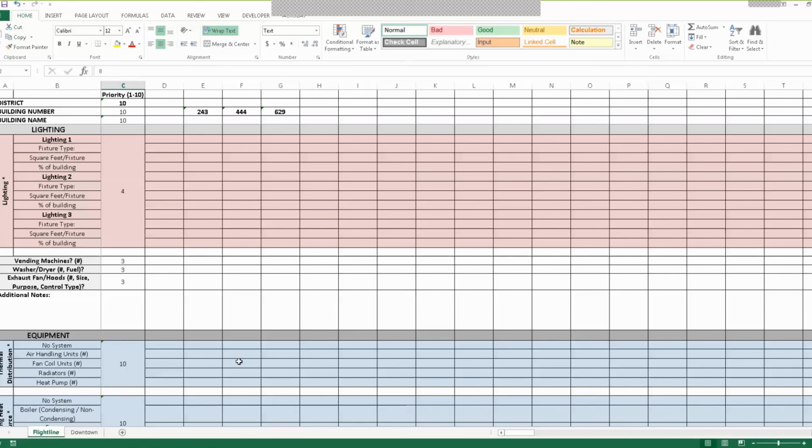Typically what happens even in older buildings, and that's why there's not a huge difference in lighting numbers going back to mid-century buildings, is that the lighting has been updated at a much higher frequency than the rest of the building. So the lighting ends up being, a lot of times, at a more modern level, even in old buildings. Now, that doesn't mean you're not going to walk into areas and still see incandescent bulbs hanging in some storerooms, or a lot of T12 sitting in places. I've gone into places and seen that as well. But in many cases, a lot of that stuff has already been updated.